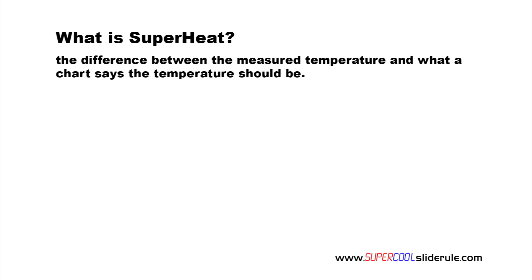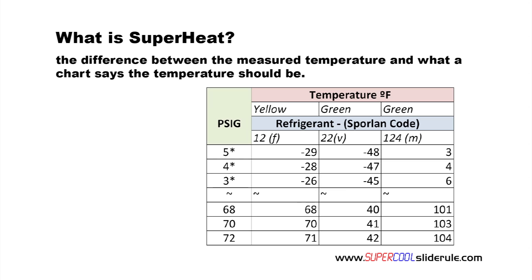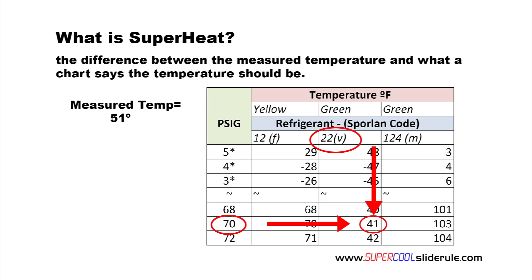Here's an example. If we reference a temperature pressure chart for R22, we will note that at 70 PSI, our temperature should be 41 degrees. If we measure the temperature of the refrigeration suction line and it is actually 51 degrees, this is 10 degrees warmer than it should be. So our superheat is 10 degrees.